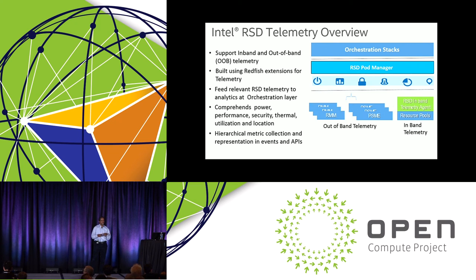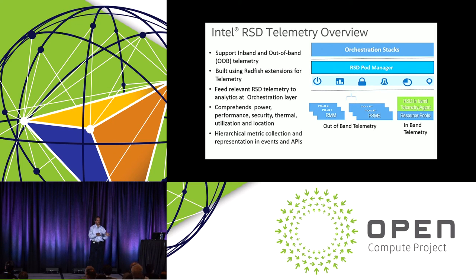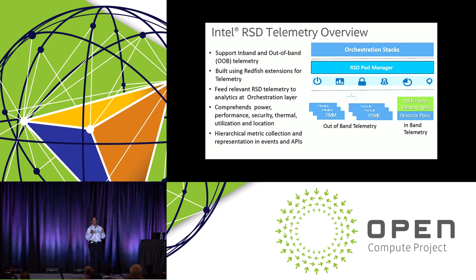The second future area is telemetry, also built on top of Redfish. There are extensions in Redfish for telemetry that allow you to feed all the information — sensors, temperature, various levels of sensor, power, performance, security (meaning 'is this the right platform, and can I release the key that unlocks storage on this box?'), utilization, and location. Location is what I was talking about — not GPS location, but relative location within a failure domain. You create an identity of the failure domain and expose it up to software so they can make smart decisions based on the failure domain.